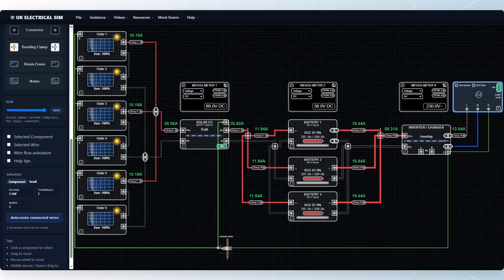If they eventually reach the low cutoff point, which is set to around 10% in the simulator, the inverter charger will stop inverting and move into an idle state to protect the batteries. Once the batteries have recharged to the restart level, the inverter can start again and the process continues.